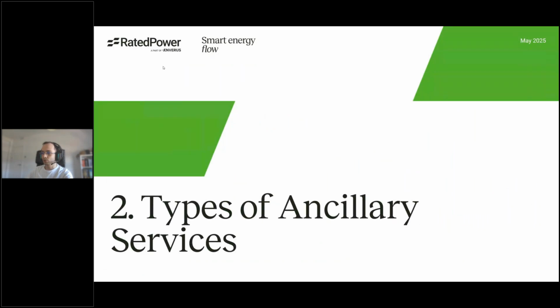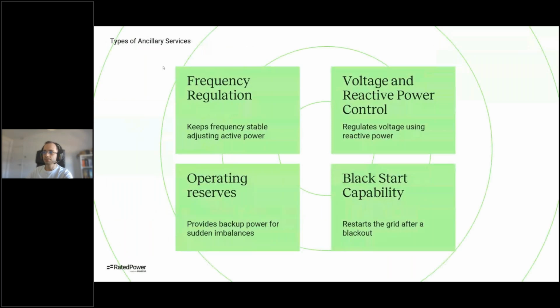So now let's go a bit into types of ancillary services, and we will highlight four of them. The main four are, first, frequency regulation. This is just keeping the frequency stable at 50 hertz in Europe, for example, or 60 in the United States. This is achieved by adjusting the active power. If we increase the active power, we will increase the frequency. If we decrease the active power, we will reduce the frequency. Then voltage and reactive power control. Same idea: we regulate voltage through reactive power, injecting or absorbing. Then operating reserves, which provide backup power for sudden imbalances in the grid. And finally, black start capability, which allows restarting the grid after a blackout.